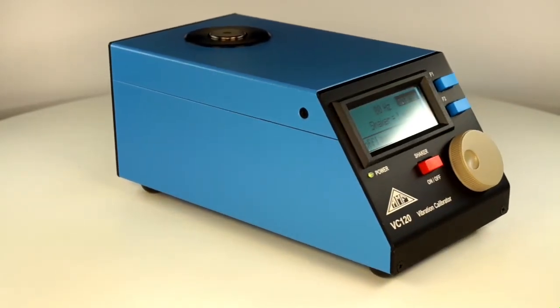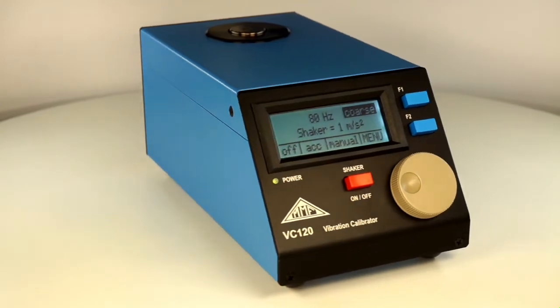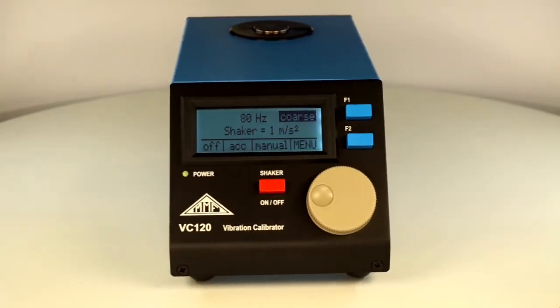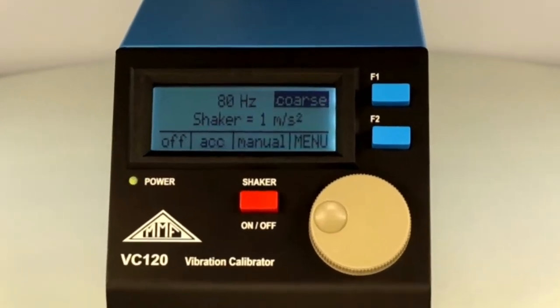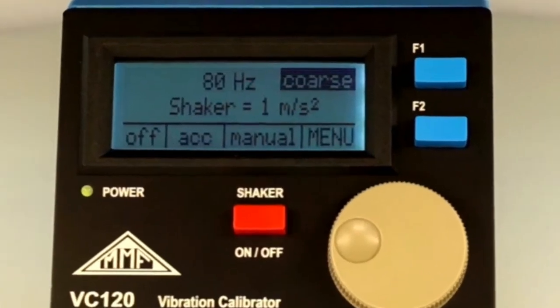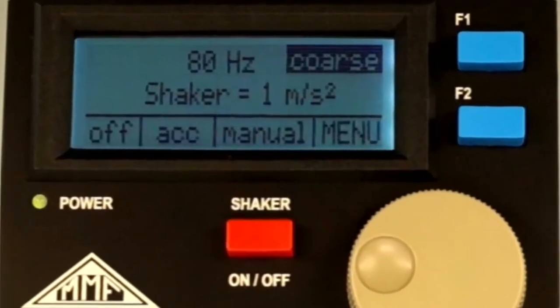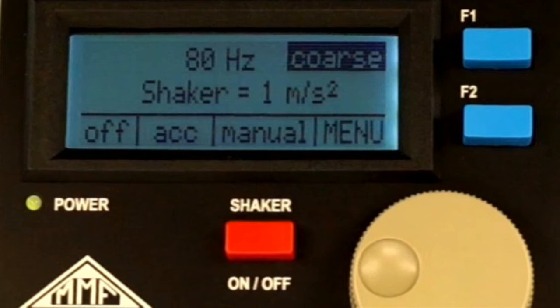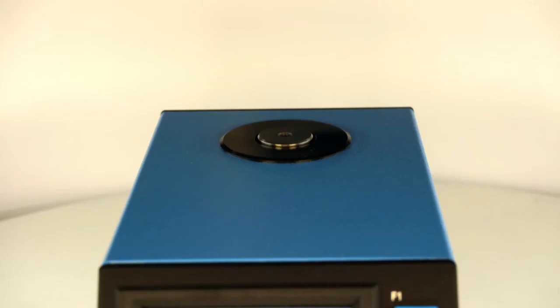The measured sensor sensitivity is shown on the LCD display at the front of the instrument. All other controls are located at the front of the instrument, including an LED indicating battery operation. The instrument is simple and intuitive to operate using the 3 buttons and shuttle wheel. Now we'll demonstrate how to calibrate an accelerometer without connecting to a PC.